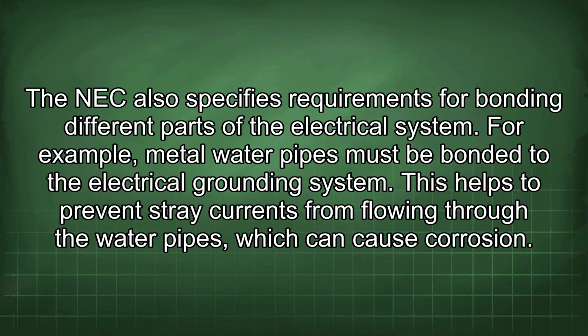The NEC also specifies requirements for bonding different parts of the electrical system. For example, metal water pipes must be bonded to the electrical grounding system. This helps to prevent stray currents from flowing through the water pipes, which can cause corrosion.